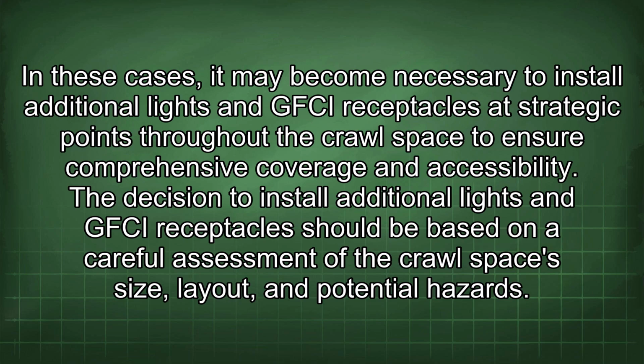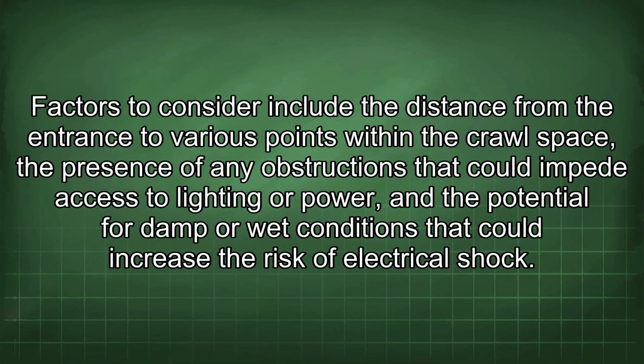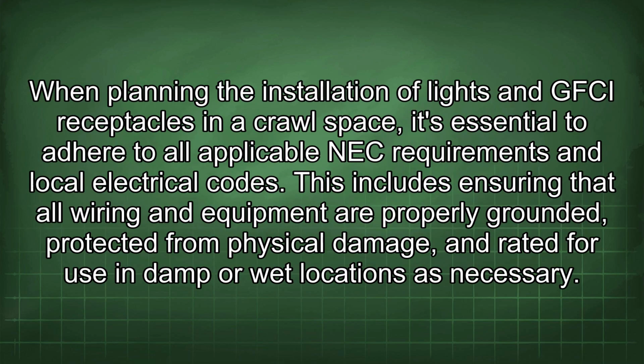The decision to install additional lights and GFCI receptacles should be based on a careful assessment of the crawl space's size, layout, and potential hazards. Factors to consider include the distance from the entrance to various points within the crawl space, the presence of any obstructions that could impede access to lighting or power, and the potential for damp or wet conditions that could increase the risk of electrical shock. When planning the installation of lights and GFCI receptacles in the crawl space, it's essential to adhere to all applicable NEC requirements and local electrical codes. This includes ensuring that all wiring and equipment are properly grounded, protected from physical damage, and rated for use in damp or wet locations as necessary.